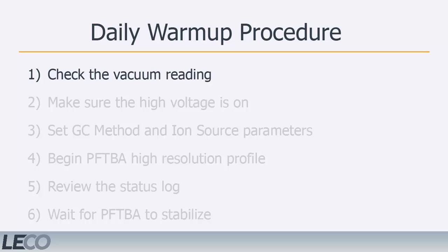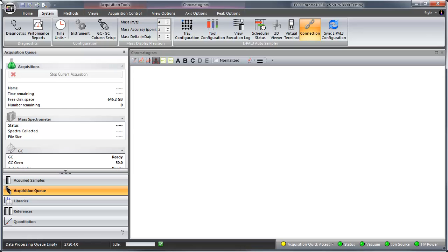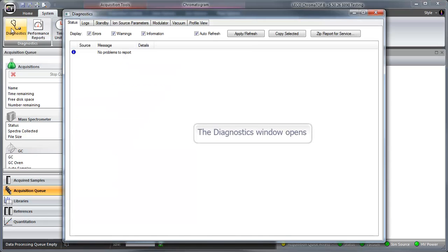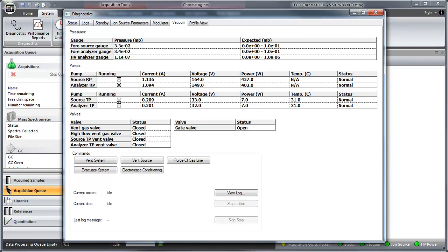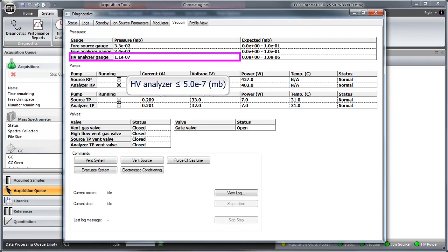Step 1. Check the vacuum. Before operating the system, check the vacuum tab in Diagnostics to confirm that the analyzer vacuum is reading below 5e⁻⁷ millibar.